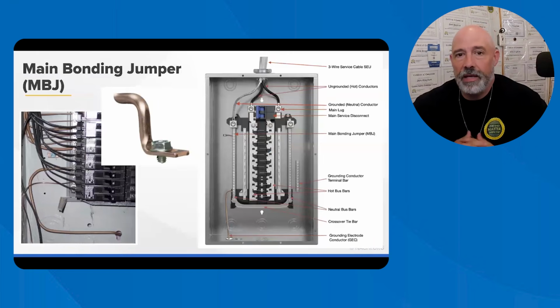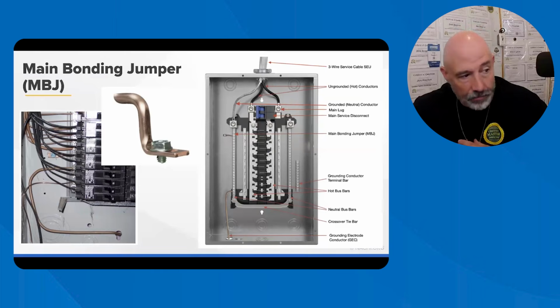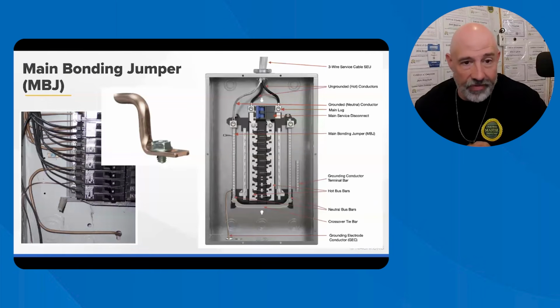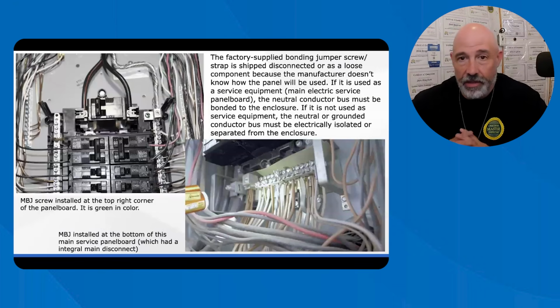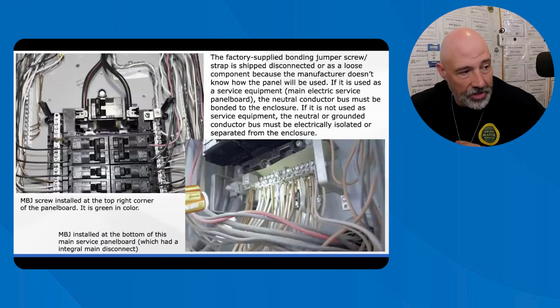The main bonding jumper wire. This is the main service disconnect: the two hot conductors connect to the main breaker, and the neutral conductor connects to the neutral bus bar. That's the main jumper, and you can see a picture of that right there. And some other pictures here where you can see the MBJ screw installed at the top right corner there.